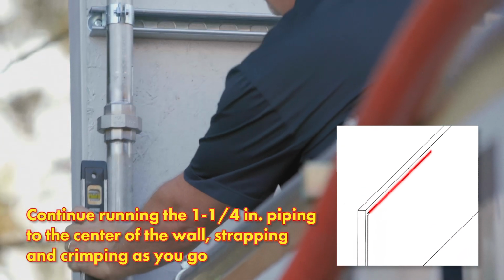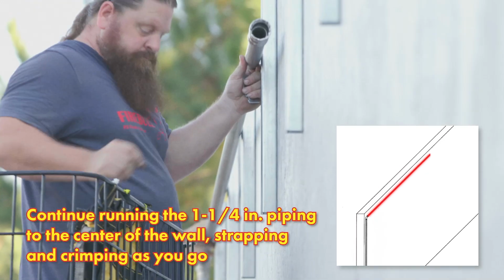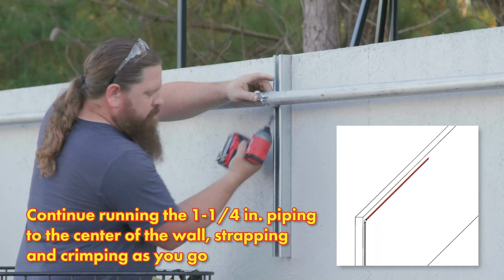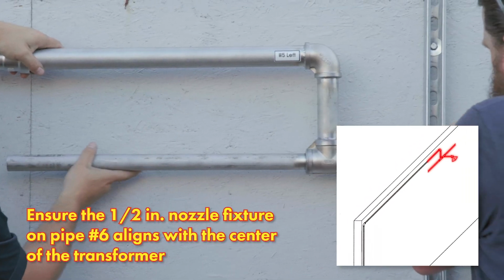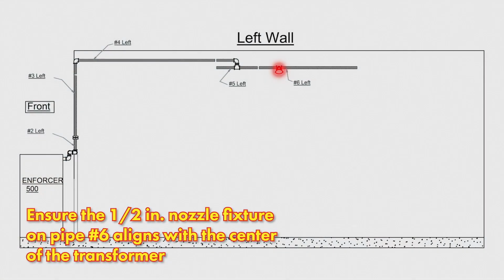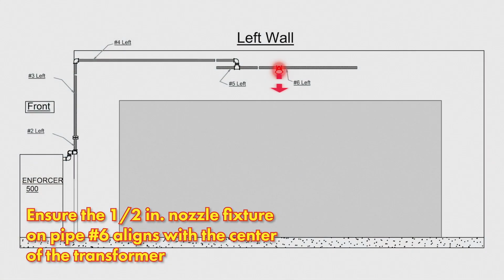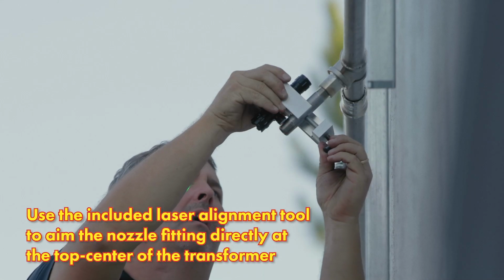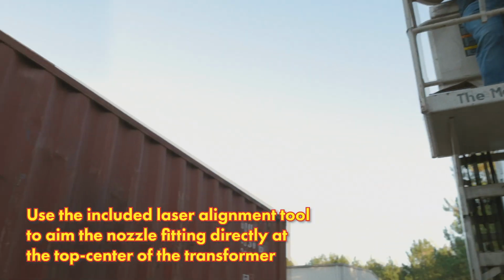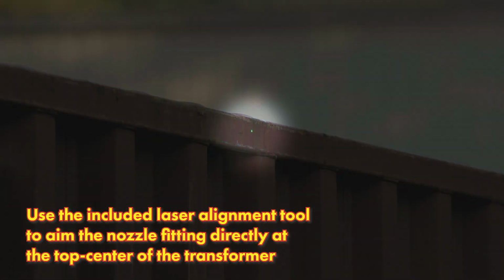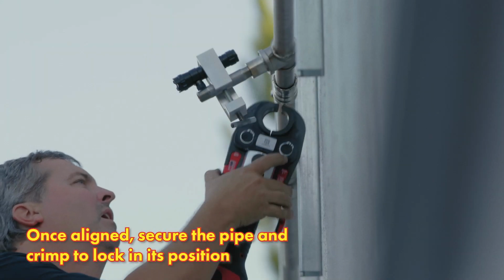Continue running the 1 1/4 inch piping to the center of the walls, strapping and crimping the pipe as you go. Be sure to measure the piping accordingly to ensure the 1/2 inch nozzle fitting on pipe number 6 aligns with the center of the transformer. Use the included laser alignment tool to aim the nozzle fitting directly at the top corner and as close to the center of the transformer as possible. Once aligned, secure the pipe and crimp it to lock in its position.